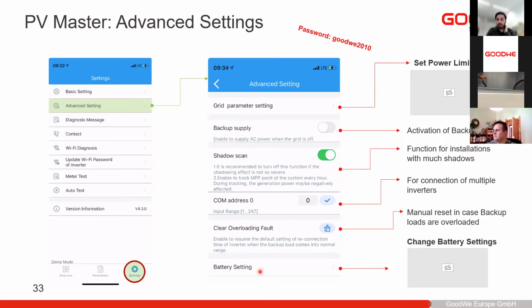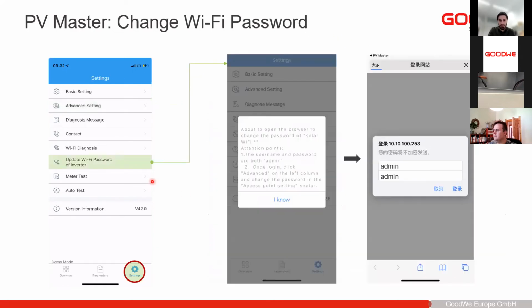And here on battery settings, it's also possible to change the specific battery configurations. In most cases, especially if using a three-phase inverter, this will be done automatically because it will communicate with the BMS of the battery and get all the necessary settings. In some cases, on the battery settings you can also choose the specific DoD settings for the backup and on-grid connection. You can have different settings for how much you want the battery to discharge or how much capacity you want to save for specific situations.